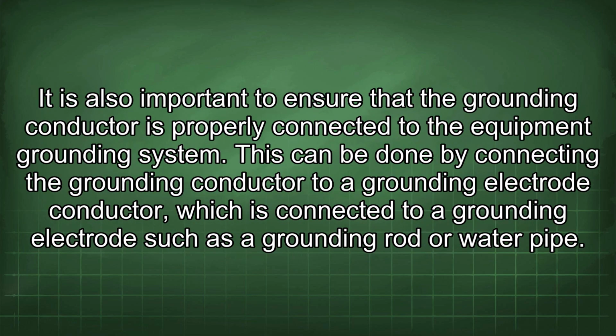It is also important to ensure that the grounding conductor is properly connected to the equipment grounding system. This can be done by connecting the grounding conductor to a grounding electrode conductor, which is connected to a grounding electrode such as a grounding rod or water pipe.